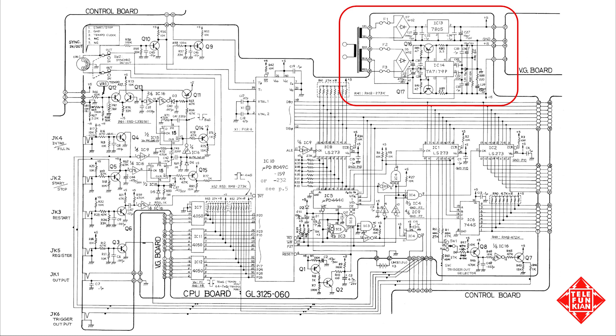The schematic for the power supply in the CR8000 can be found on pages 6 and 14 of the service manual. The supply itself is on the CPU PCB, with the transformer and power switch mounted separately. It produces 3 independent rails of smooth DC: +5, +15, and -15 volts. It's a relatively straightforward linear supply with a couple of components that might be hard to source if something should go wrong, and we'll describe these in a moment.